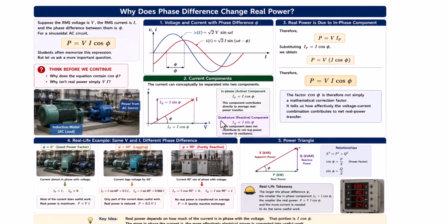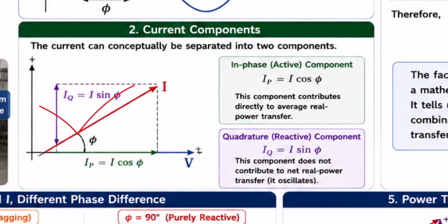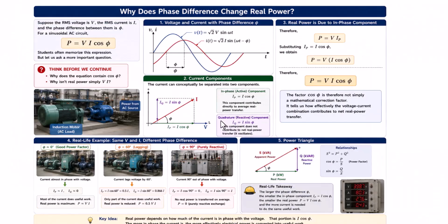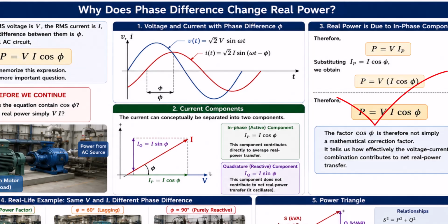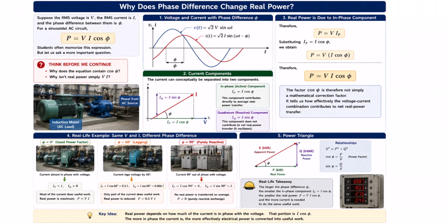The current can conceptually be separated into two components. The component in phase with the voltage is I_P is equal to I cos phi. This component contributes directly to the average real power transfer. The perpendicular reactive component is I_Q is equal to I sin phi. Therefore, P is equal to V times I_P. Substituting, I_P is equal to I cos phi, and finally we obtain P is equal to V times I cos phi. The power factor, the factor cos phi, is therefore not simply a mathematical correction factor. It tells us how effectively the voltage current combination contributes to net real power transfer.